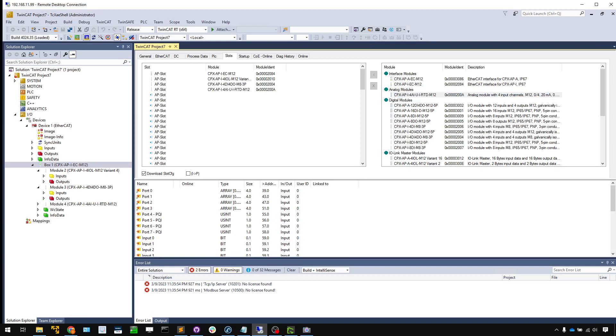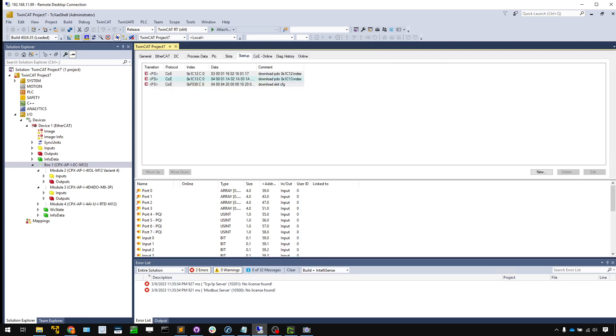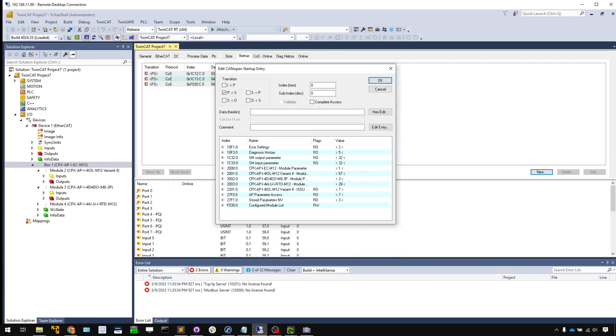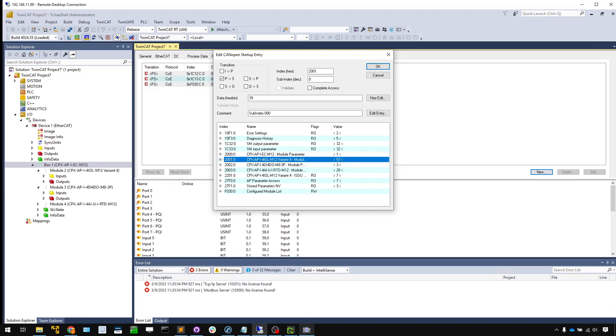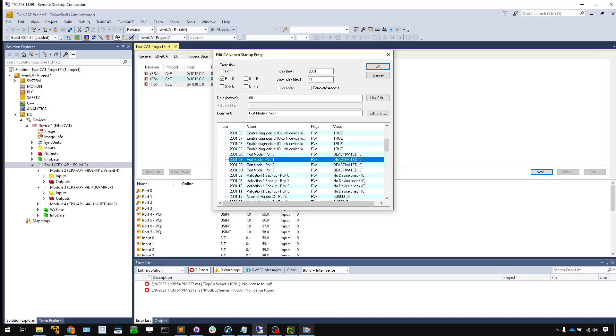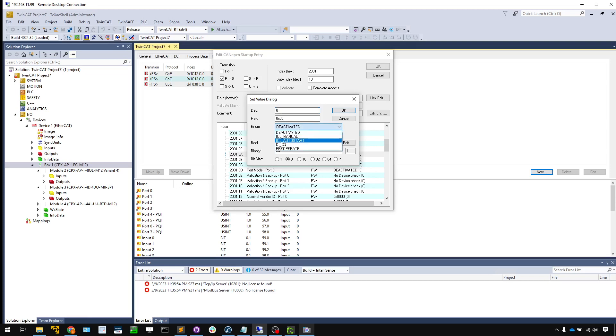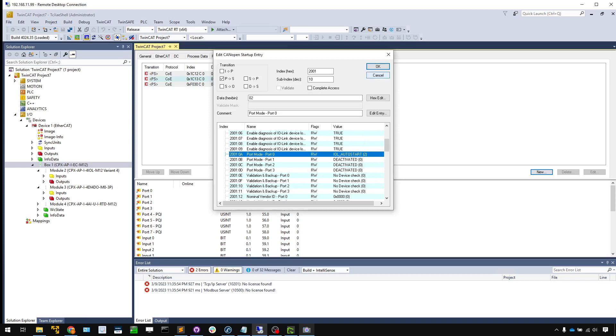The basic configuration is finished. The next step is to configure startup parameters. There are several ways — you can use function blocks to access CoE objects — but the easiest way is the Startup tab, where you can configure which parameters to write on startup and with what values. Go to the Startup tab, press New. The first thing we need to configure is the IO-Link module: go to the IO-Link M12 module and choose Port Mode, Port 0, then change it to IOL Auto Start.